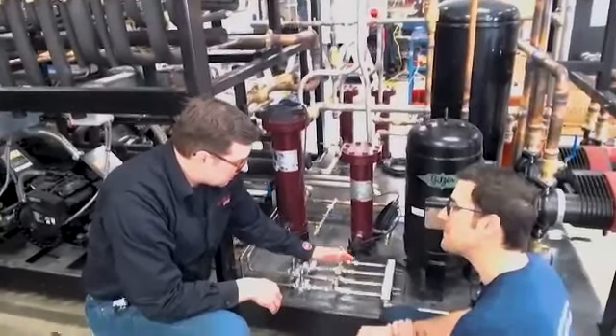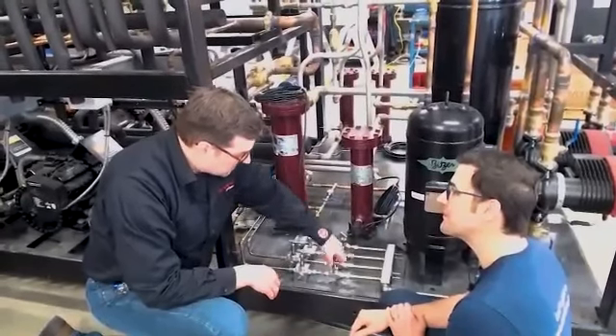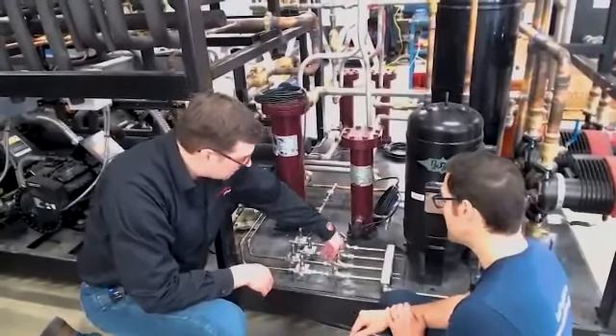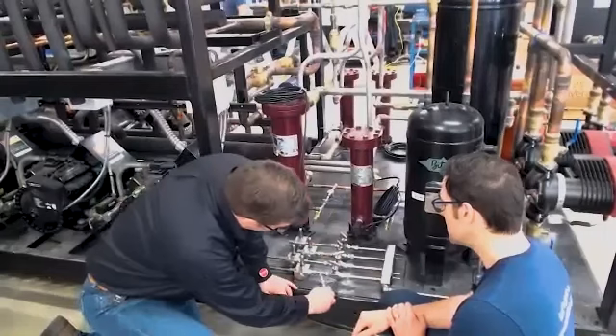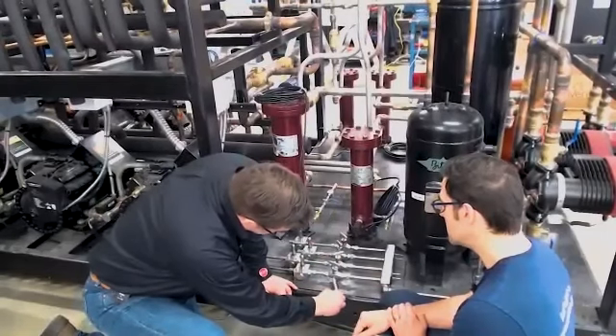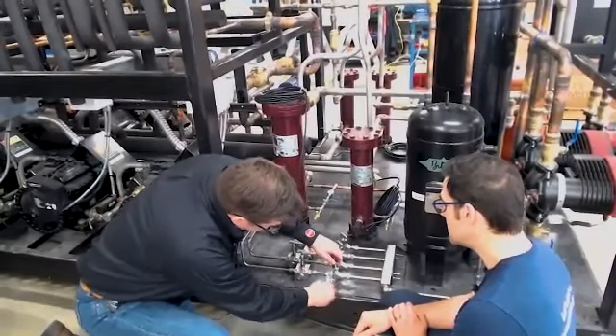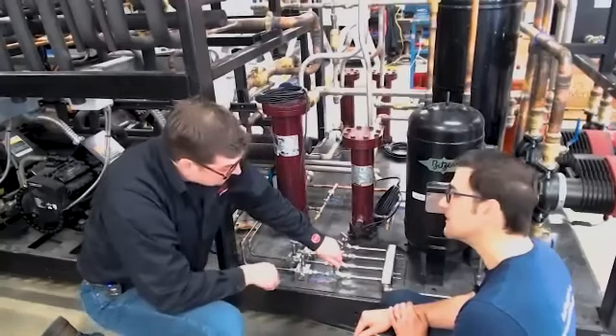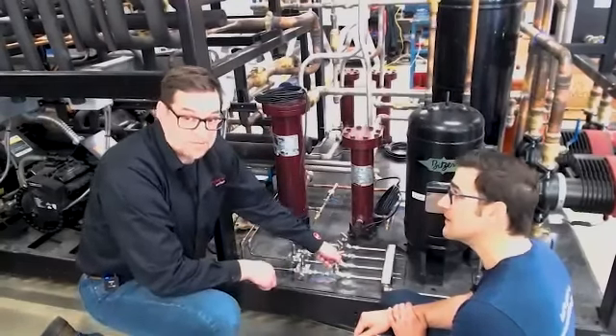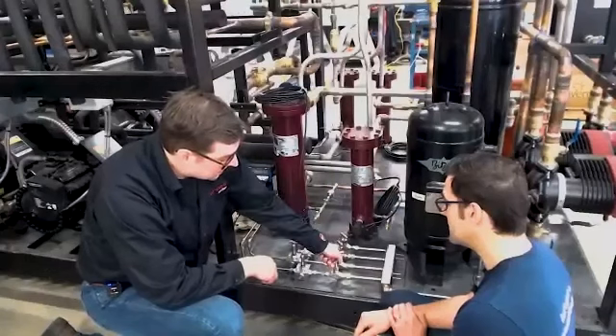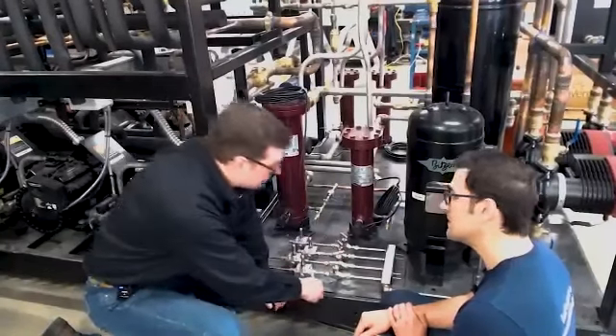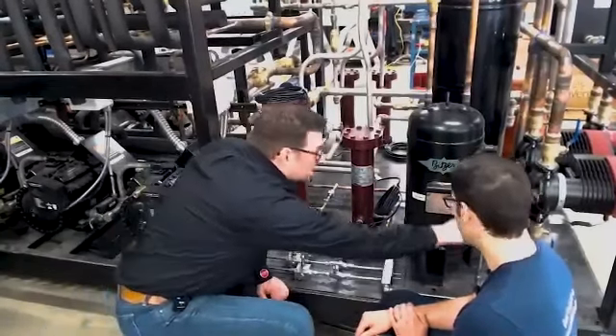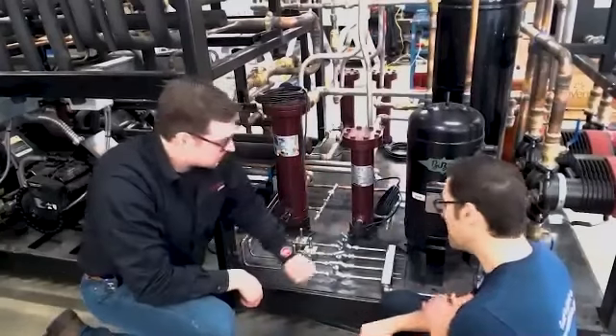So these are needle valves, and basically I can close it all the way down. My oil gas mixture is going to come in, she's going to drop down in the bottom. She's fully closed, nothing's going to move. This is not a depressurization valve - that's really important. This is a metering device so I don't flood my oil receiver.